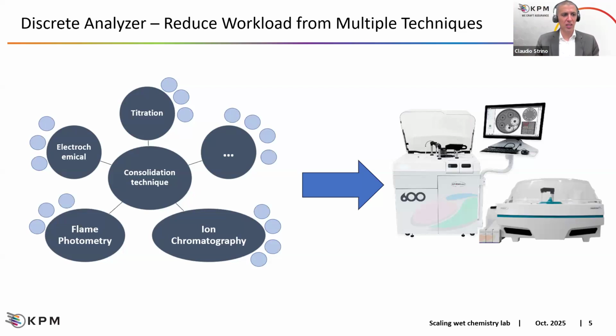While with ion chromatography it is true that we may have multiple parameters at once, the average time is around 20 minutes per sample. So consider 200 samples to be tested: on the SmartChem 600, we are shorter than an hour for testing. On the ion chromatography, we need much more time.